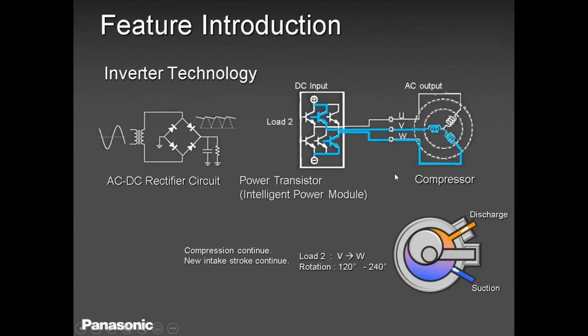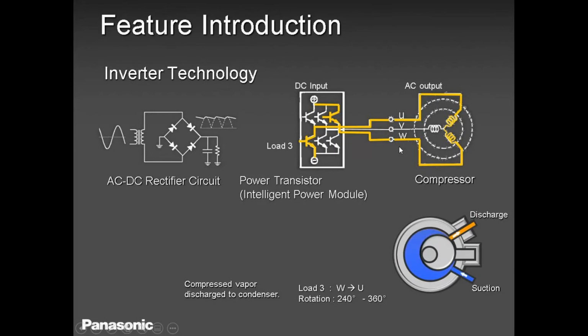But this inverter technology has a smooth start. It starts at a lower frequency, and depending on the demand from the house, from the room, from the whatever storage, it will ramp up, and it keeps ramping up, and once it gets to its required set point, it will start slowing down, and that's how you get good energy efficiency out of this compressor, and you save a lot of money. Trust me, you save a lot of money on hydro. So that's your compressor there.